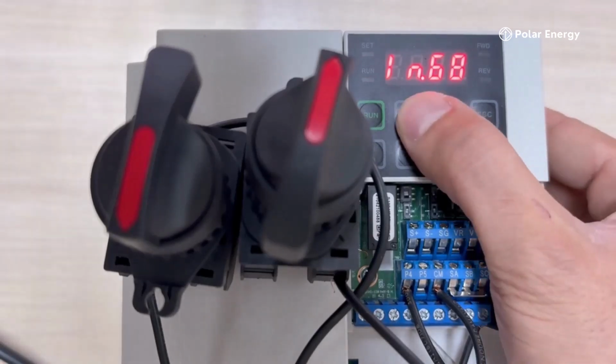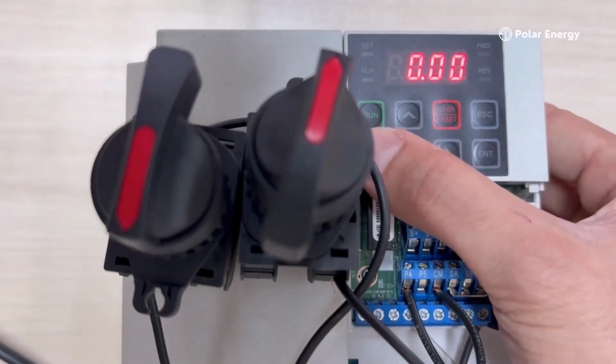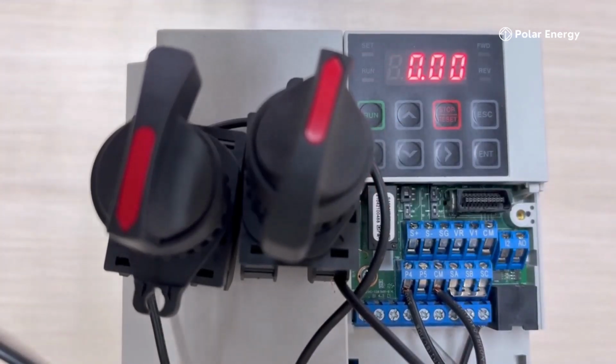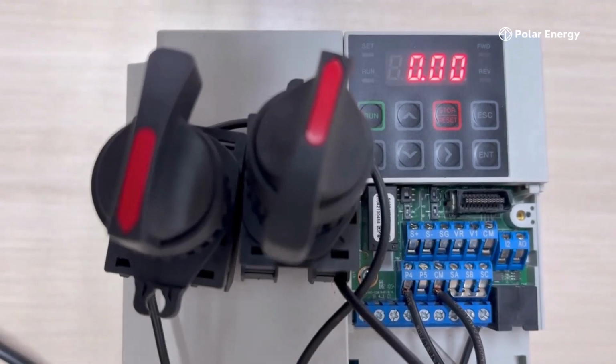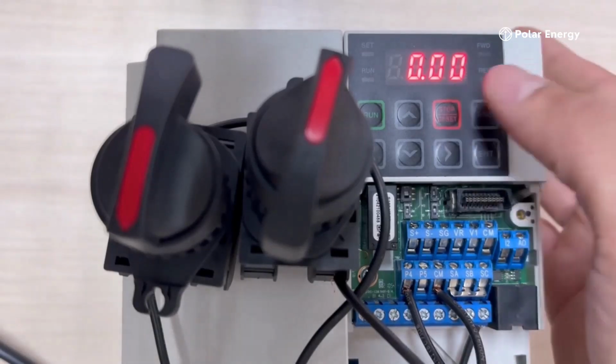As we mentioned in the speed settings, after the speed command, if my speed command is 0, this multi-step setting becomes my first speed. If a frequency value is given for the command, then the value we set in ST1 becomes my second speed. Now I've set the command to 0, so my first speed is set in parameter ST1.